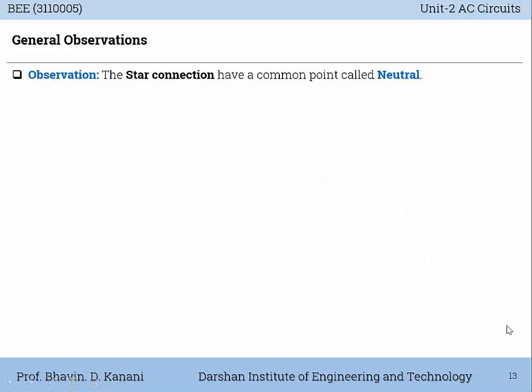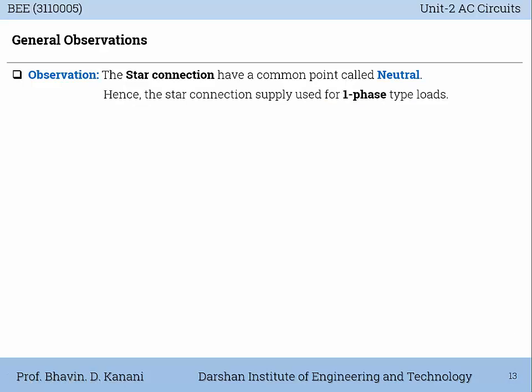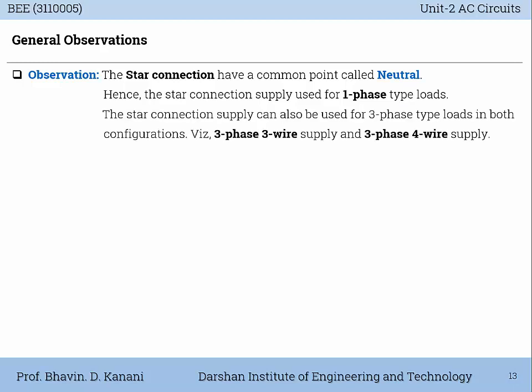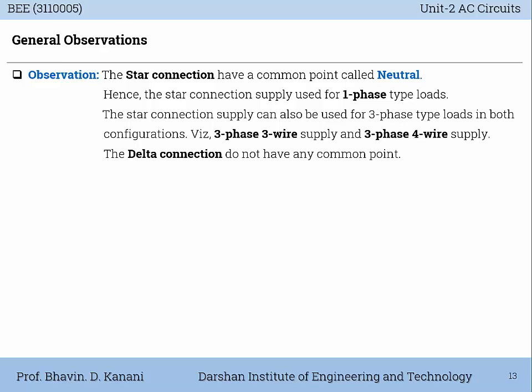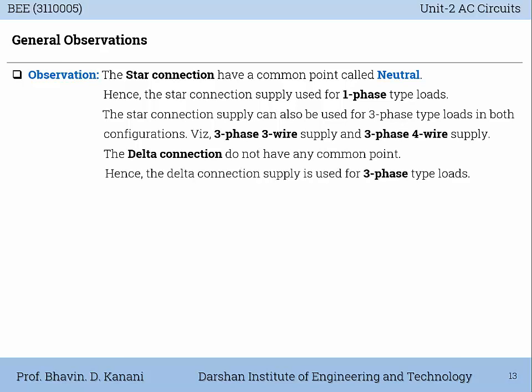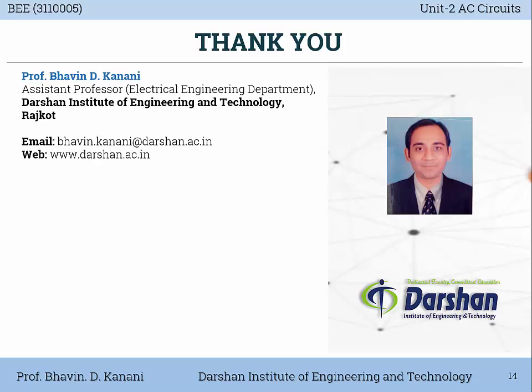General observations: The star connection has a common point called neutral. Hence, the star connection supply can be used for single-phase type loads. The star connection supply can also be used for three-phase type loads in both configurations — three-phase three-wire supply without neutral, and three-phase four-wire supply with neutral. The delta connection does not have any common point, hence the delta connection supply is used for three-phase type loads only.